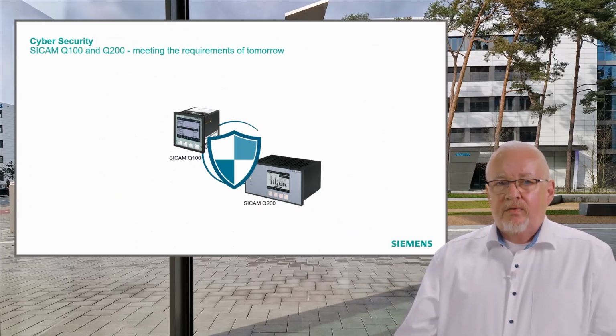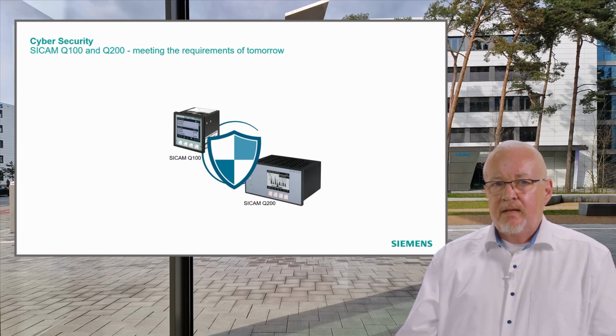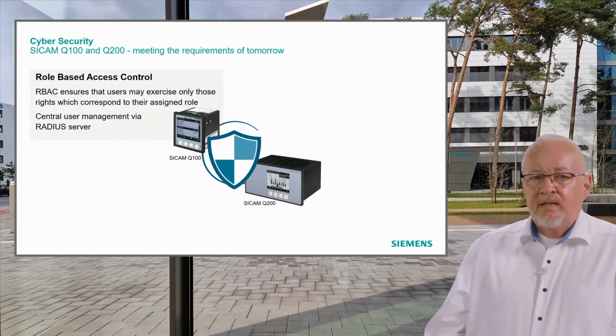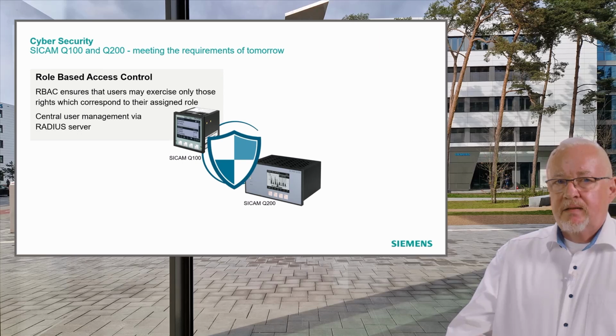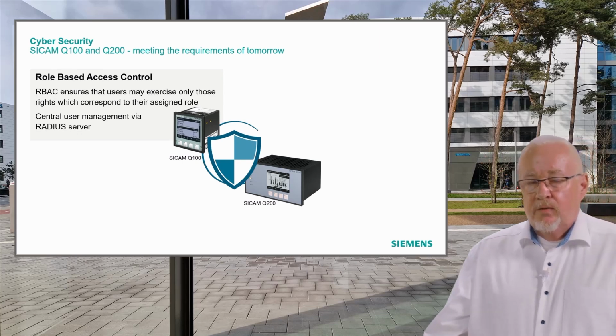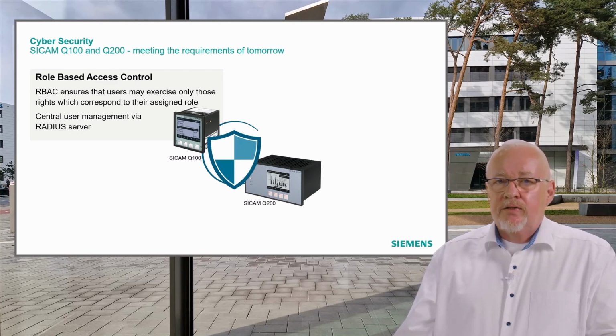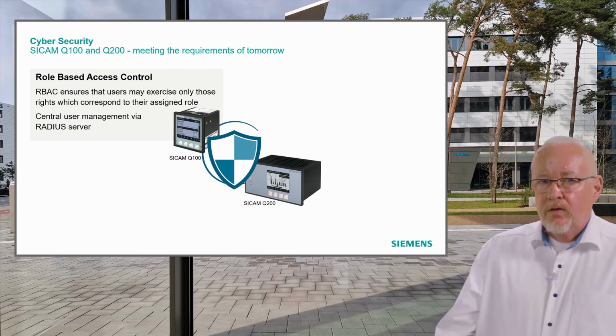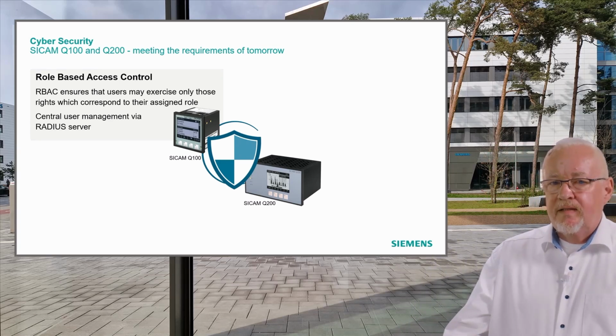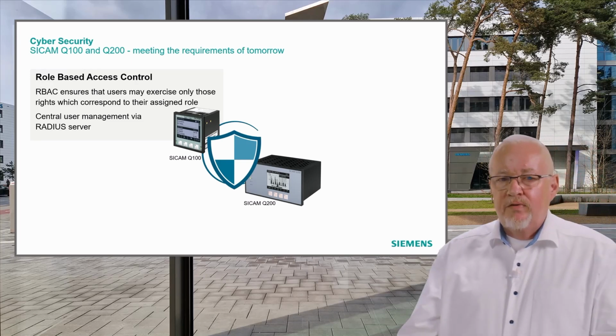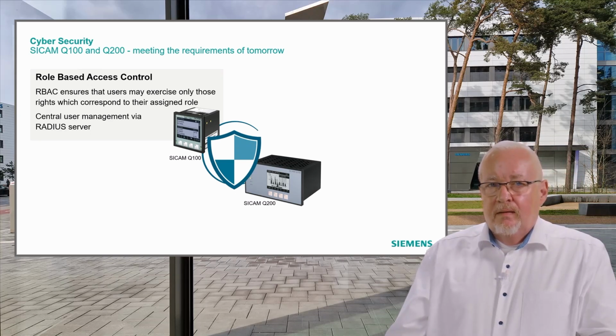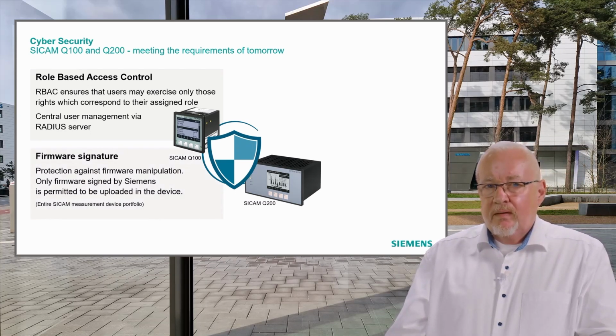Another important topic for devices which collect and transmit this kind of sensitive data is cybersecurity. We installed in both devices a role-based access control. That means role-based access ensures that the user may exercise only those rights which correspond to their assigned role. So you can scale the access to the device from reading values only up to updating firmware or deleting buffers and so on. Central user management via RADIUS server is supported.